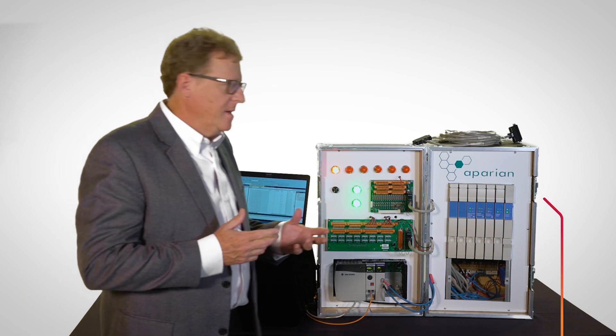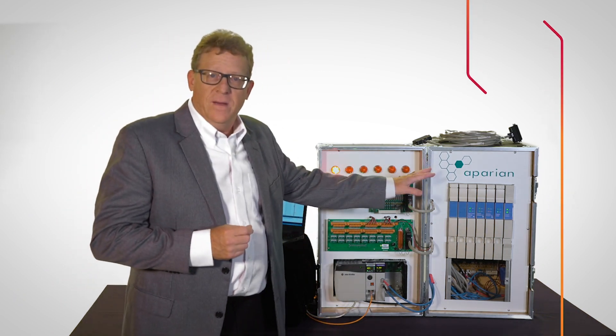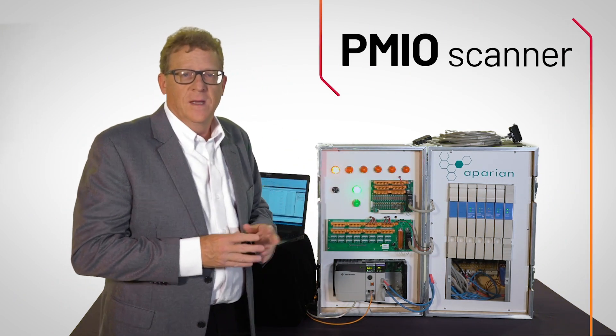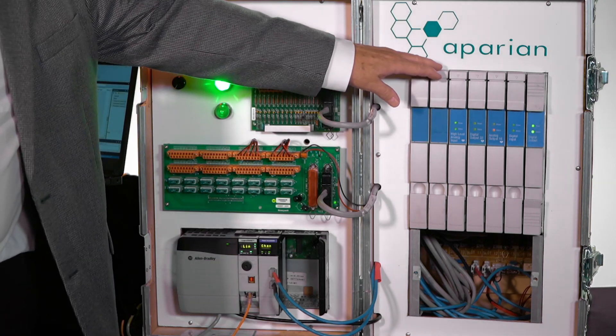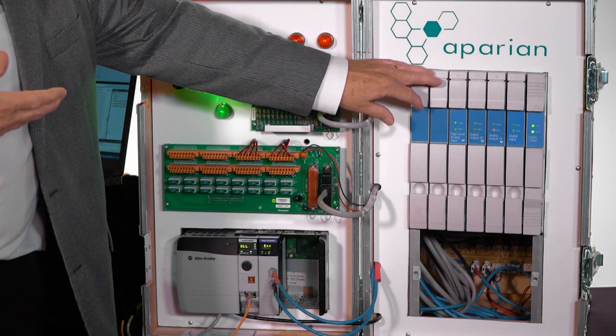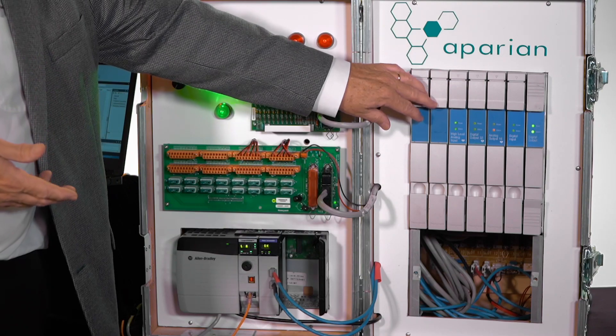What we're showing here is a demonstration of the Aparian PMIO scanner. On the right, we have the Process Manager IOP cards powered up and as you can see, running without the HPM controller.